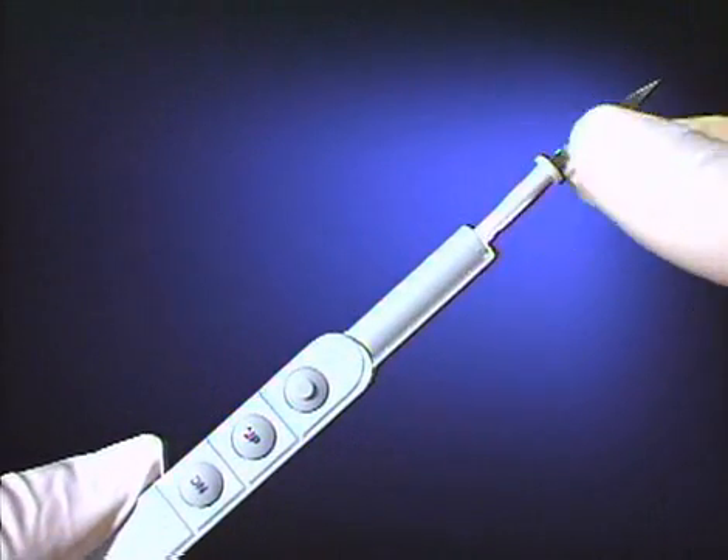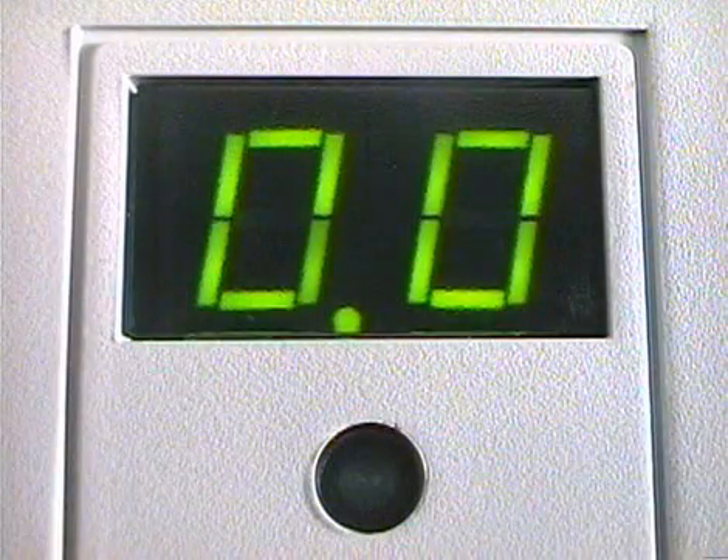The disposable electrodes are designed for use in the Hyfrecator and provide a convenient way of avoiding contamination. On all procedures, the power settings should be as low as possible to achieve the desired effect without excessive tissue destruction. While higher power settings may appear to work more quickly, they may actually produce less efficient electrodesiccation and electrocoagulation by charring the tissue, which interferes with further electrodesiccation and destruction. In addition, a thick eschar that results from an excessively high power setting may be prone to dislodge and bleed. Now, let's look at the Hyfrecator Plus in action.